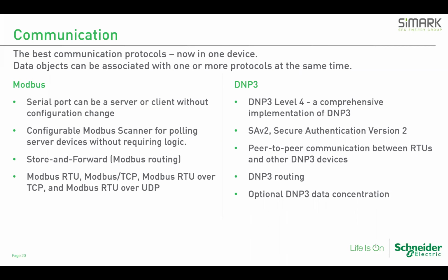An optional licensed feature, if the architecture demands it, is the ability to use a SCADAPack470 as a data concentrator for DNP3 data. So this now means information comes up from an RTU and is stored in the main data concentrator RTU for then being passed on to a SCADA host. So the SCADA host does not have to poll or reach out to those other RTUs. They can all be done by going to the single SCADAPack behaving as a data concentrator.